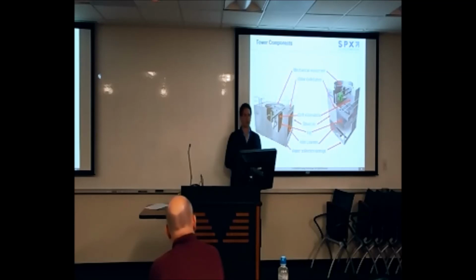It's not a huge problem for air quality, but where we run into problems with drift is when you have parking near these cooling towers, or even a doctor's office. You have doctors who have nice cars. They get little specks on their cars. They need to be cleaned. They get upset. They call us. So to avoid that, we put these drift eliminators in, which are triple pass, so that water cannot escape the tower and get outside the fan.